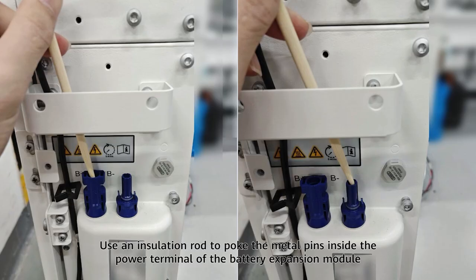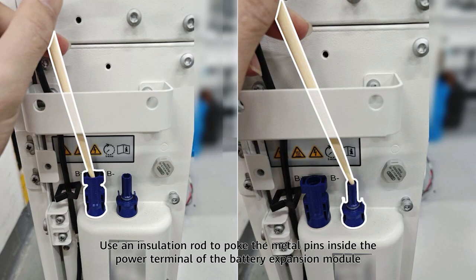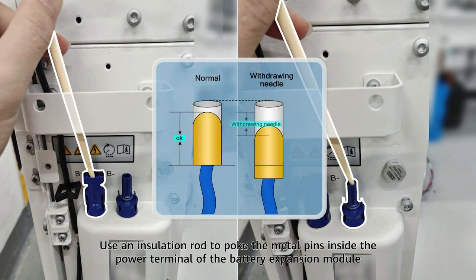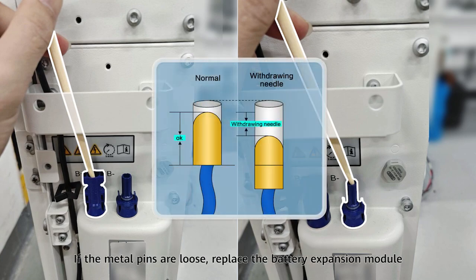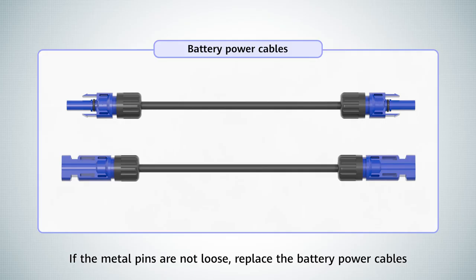Use an insulation rod to poke the metal pins inside the power terminal of the battery expansion module. If the metal pins are loose, replace the battery expansion module. If the metal pins are not loose, replace the battery power cables.